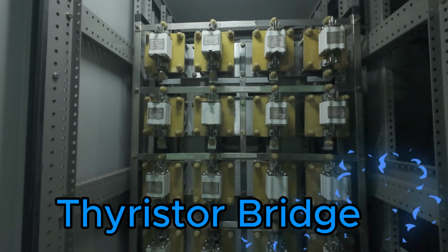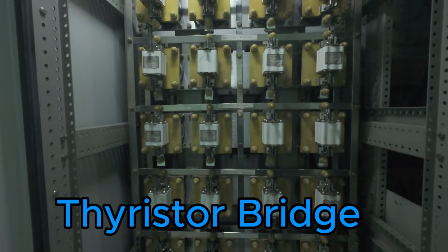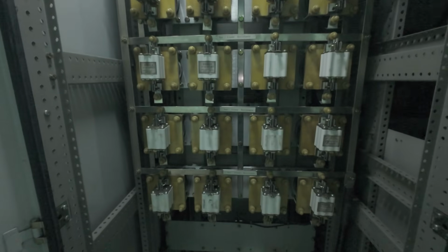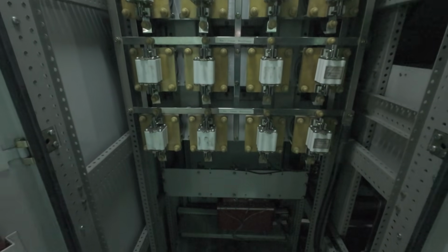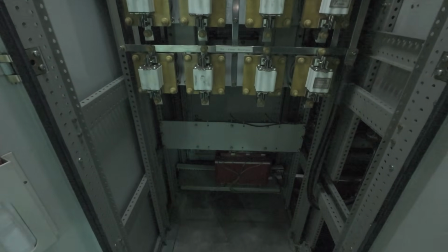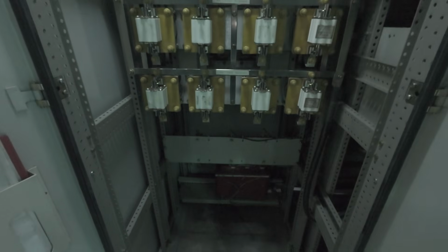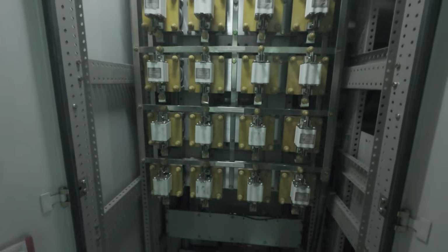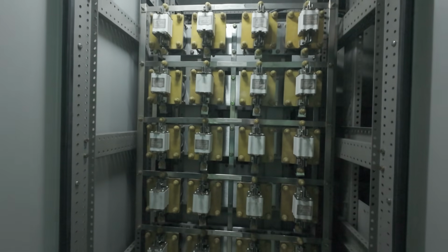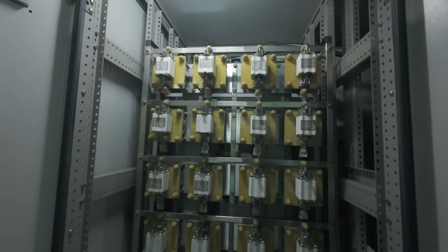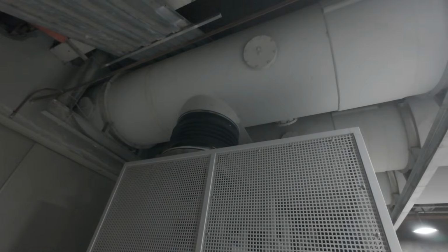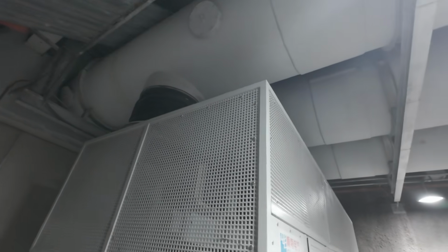That power then enters the heart of the system, the thyristor bridge. This is where the AC power becomes controlled DC current for the rotor. Inside the cabinets are electronic switches called thyristors. They open and close thousands of times every second like ultra-fast electrical gates. The AVR controls exactly when those gates fire.